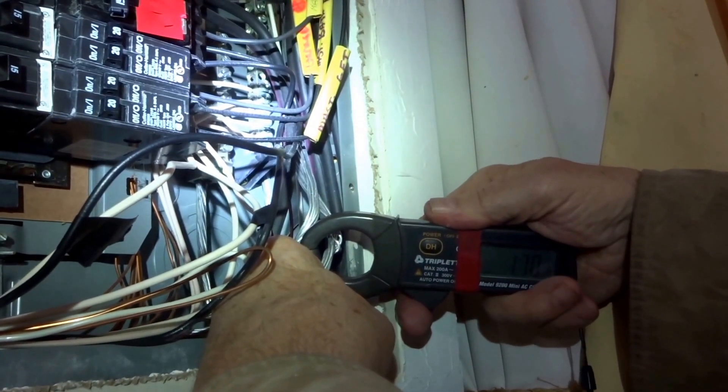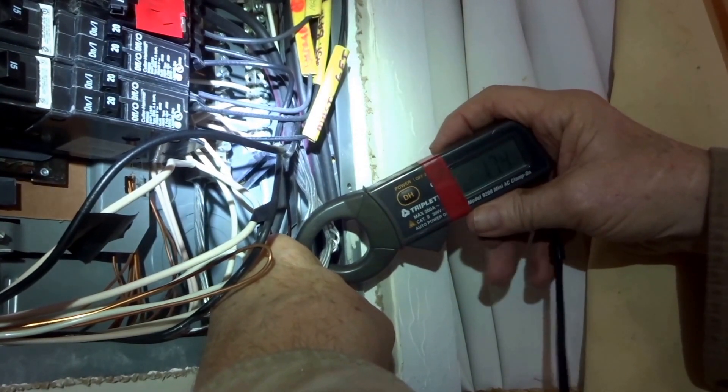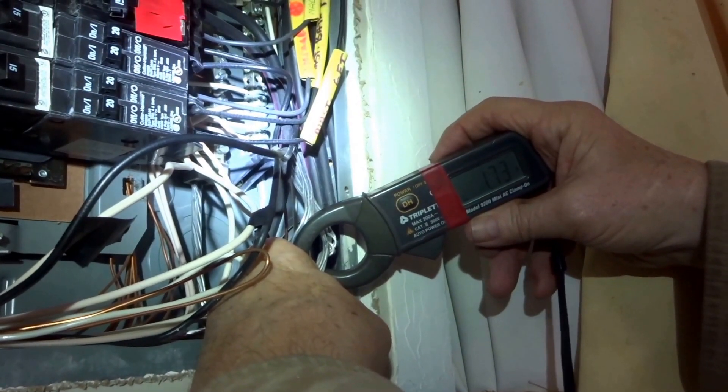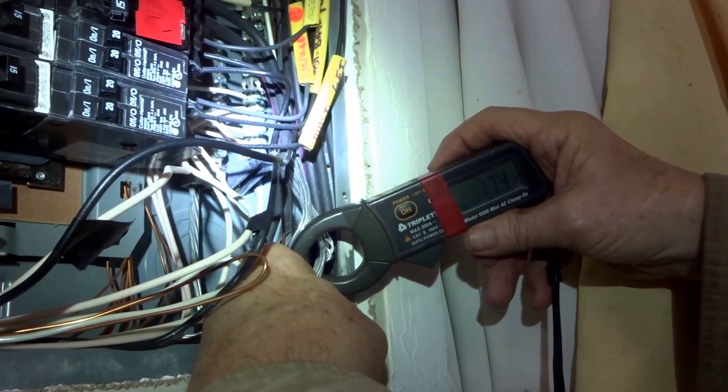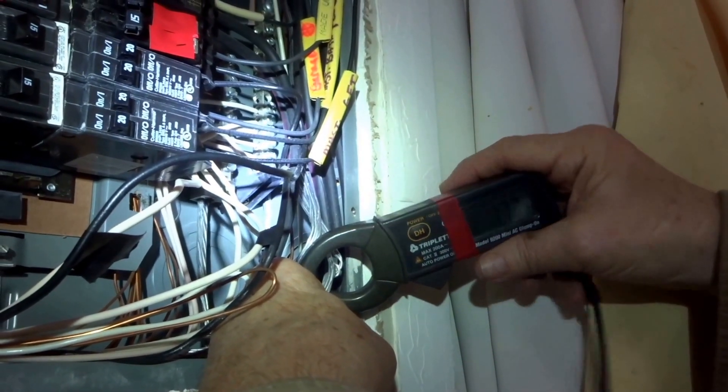That's correct. Okay, anything else you want to mention about this? No, we need to have the utility trouble crew come out and clean up the service neutrals as a starting point, and then we recheck these levels, and they will probably go down.